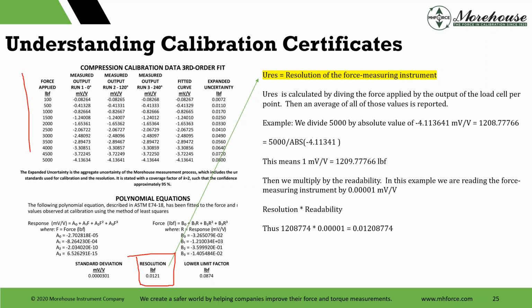Well, for each and all of these force points, we take the average and we divide it. So if we wanted to know this resolution for 5,000 pounds, we take 5,000 pounds and the absolute value of 4 millivolts per volt. We divide 5,000 by 4 point, and we get 1208.776. So that's what we're getting right here. This means 1 full millivolt equals 1,209.7766. Okay, that's good. That's 1 millivolt.